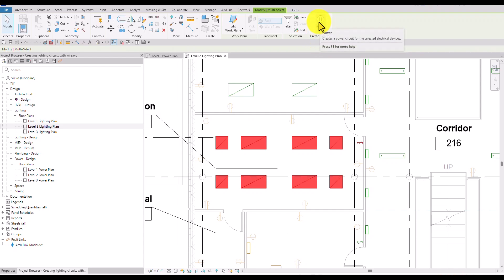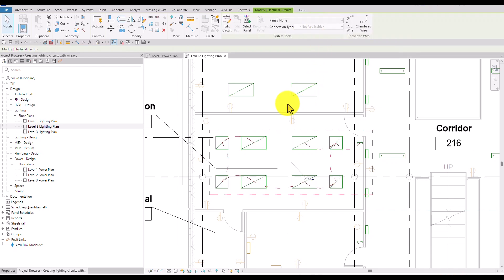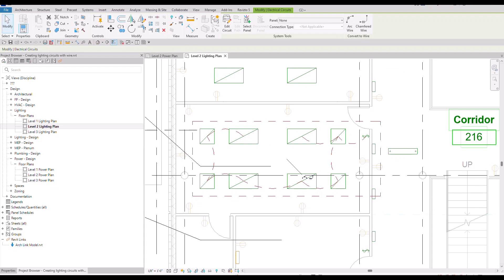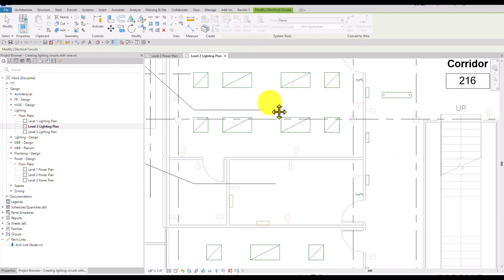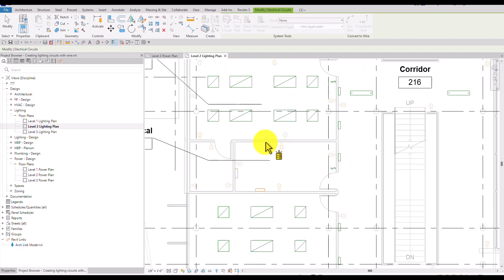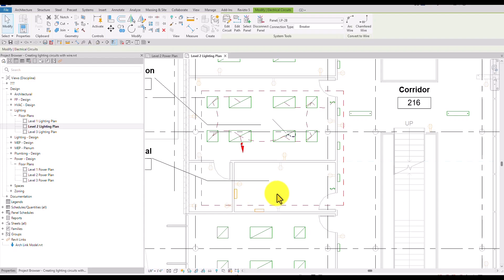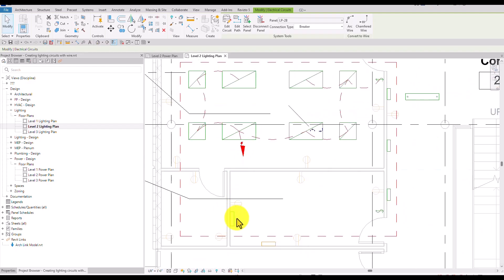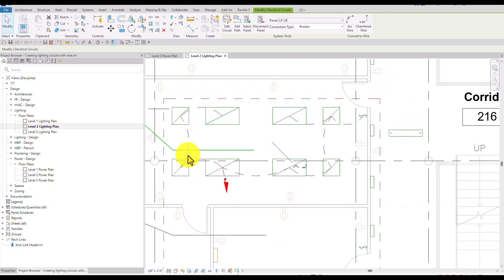With the elements selected, I'll create a system by selecting Power to create the power circuit. After that, I need to select the panel to assign the lighting devices and fixtures. You'll see red dotted lines appear showing the created circuit — this is the logical connection between elements. I'll click Select Panel and choose my lighting panel LP-2B to assign these elements to it. The red sketch graphics show the logical circuit with a home run arrow pointing toward the selected panel.